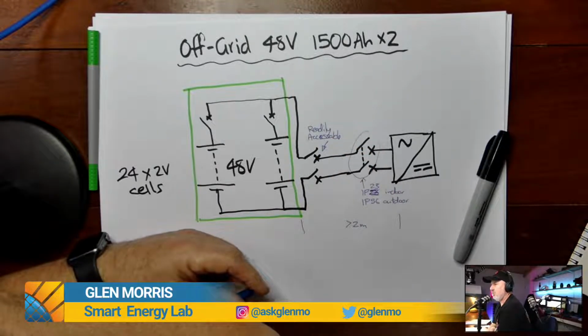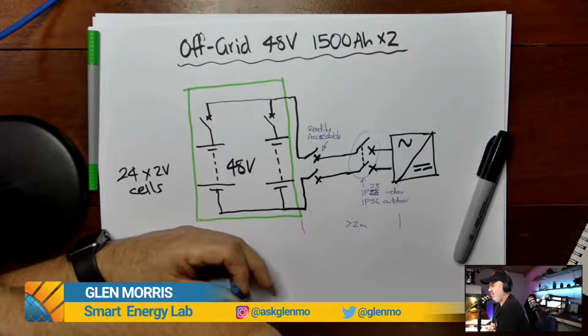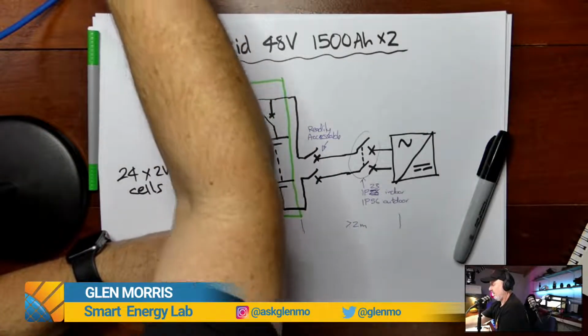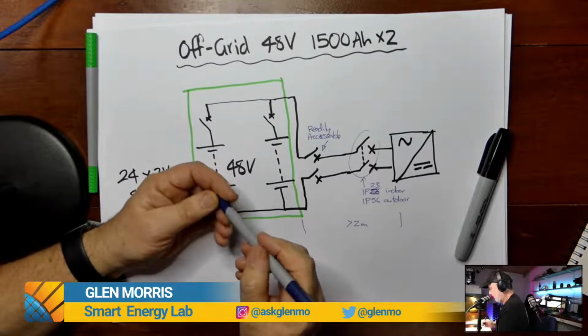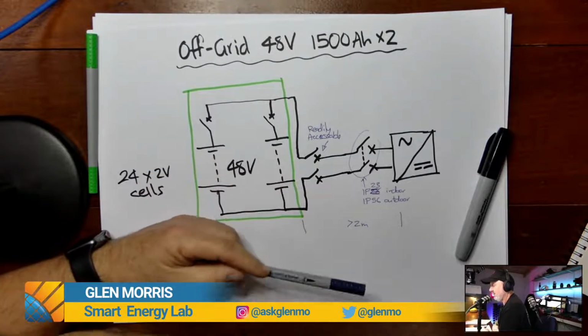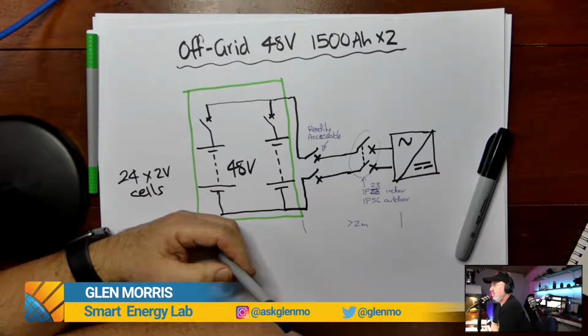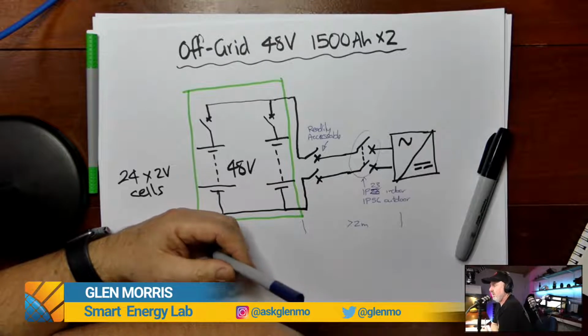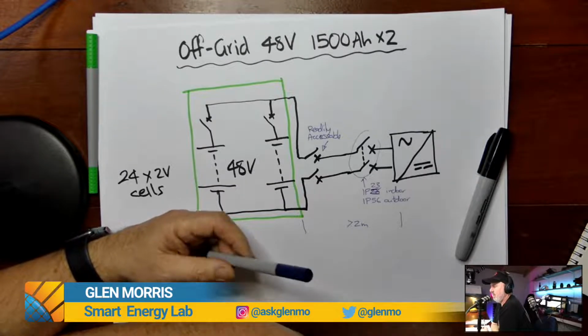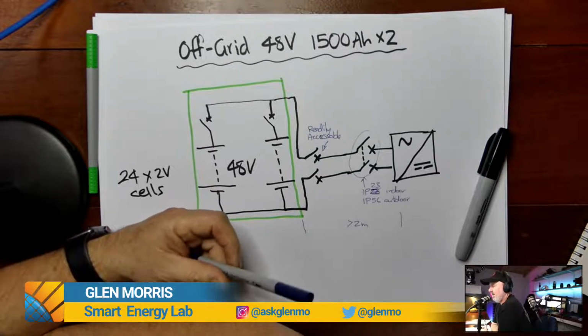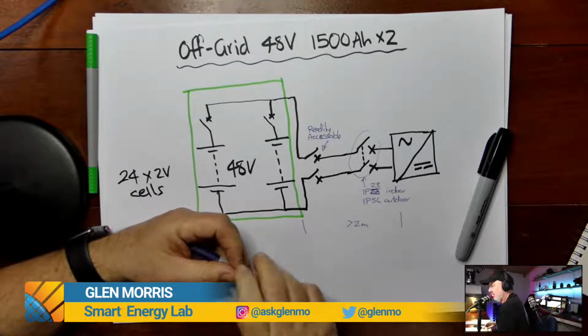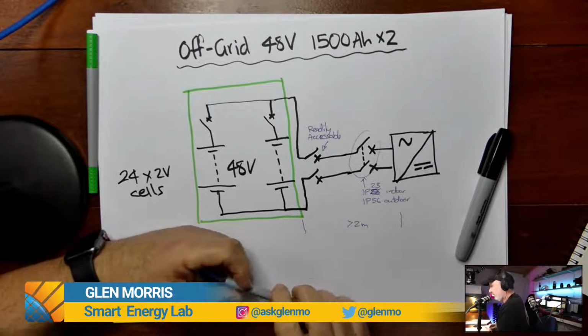And that trips up some battery systems that have integrated isolation, but you need a tool to access it. It might require an Allen key, for instance, to get to the isolator, and therefore it's not really suitable as a piece of equipment that the system operator, who may not be a licensed electrician, can access the internals of the battery to isolate it.